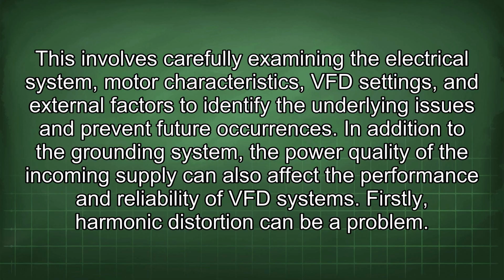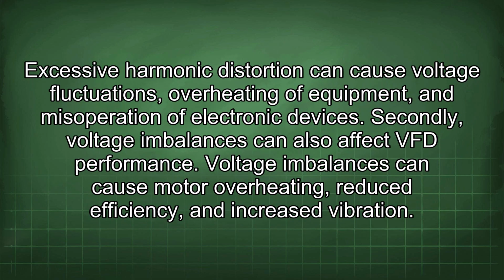prevent future occurrences. In addition to the grounding system, the power quality of the incoming supply can also affect the performance and reliability of VFD systems. Firstly, harmonic distortion can be a problem. Excessive harmonic distortion can cause voltage fluctuations, overheating of equipment, and misoperation of electronic devices. Secondly, voltage imbalances can also affect VFD performance. Voltage imbalances can cause motor overheating, reduced efficiency, and increased vibration.